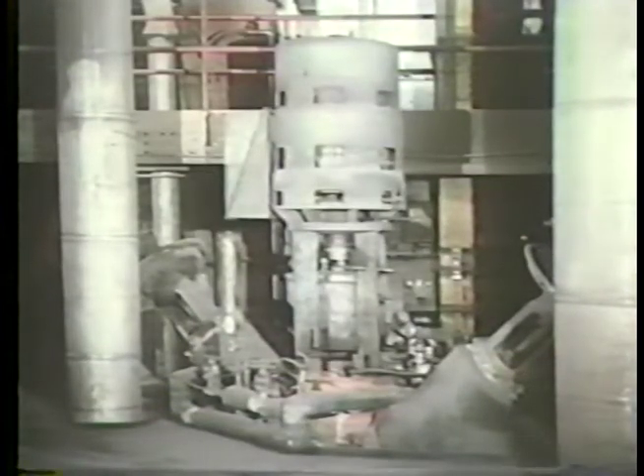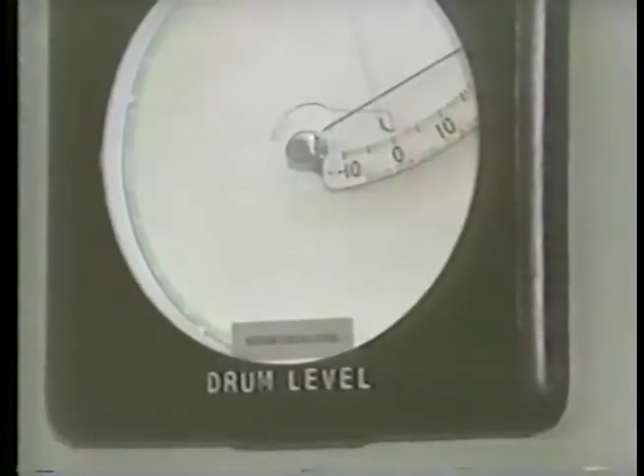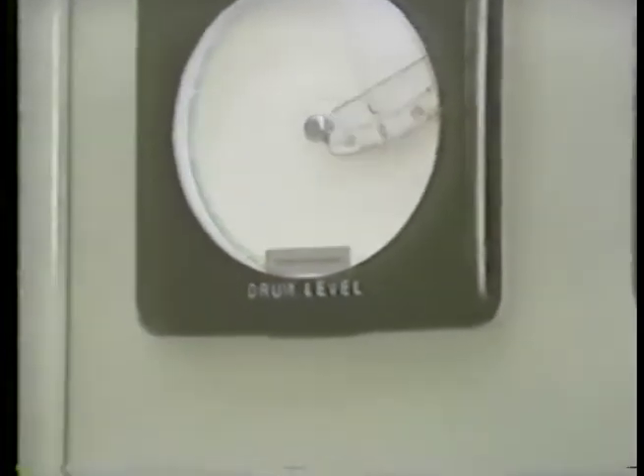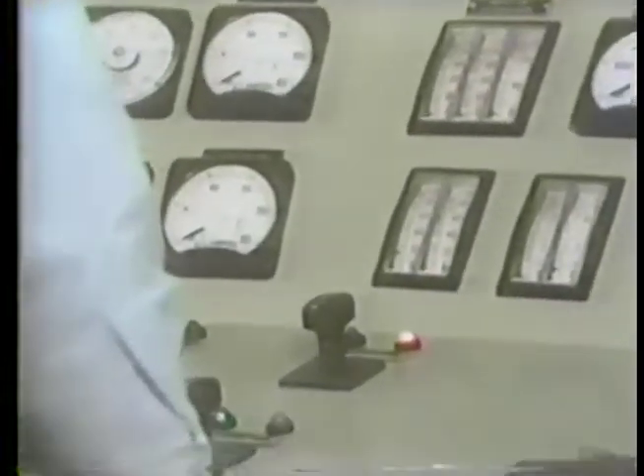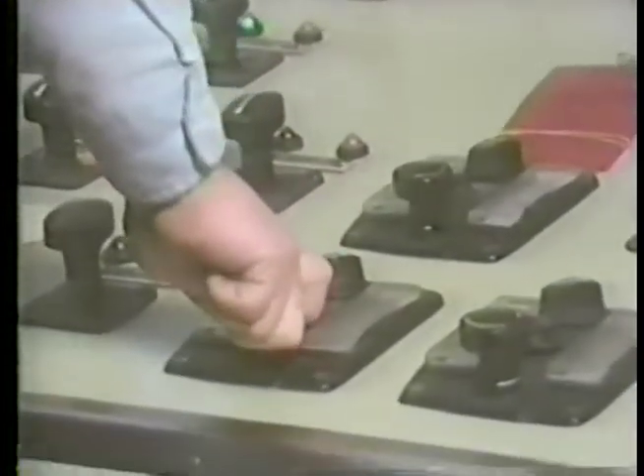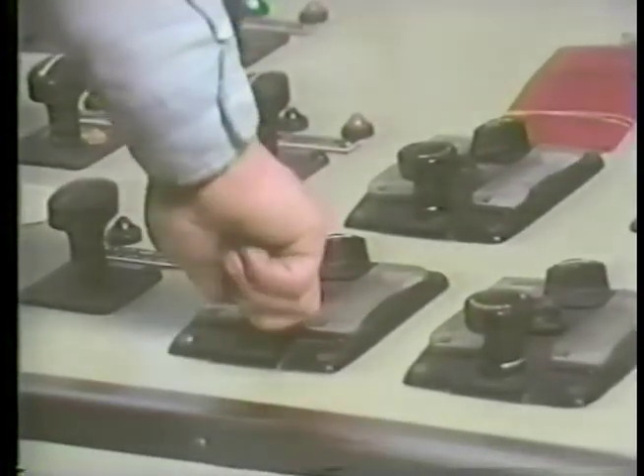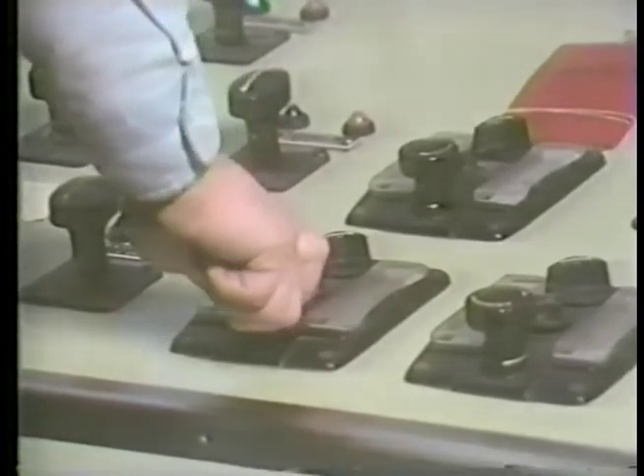On this boiler, water wall circulation is initiated by starting the boiler water circulating pumps. When the appropriate pumps are started, the operator monitors the drum level and anticipates the decrease in level. He then makes any adjustments necessary to maintain the proper level in the drum. At this point, what we've done is establish the continuous circulation of boiler water to the drum, downcomers, lower headers, water wall tubes, outlet headers, and back to the drum.